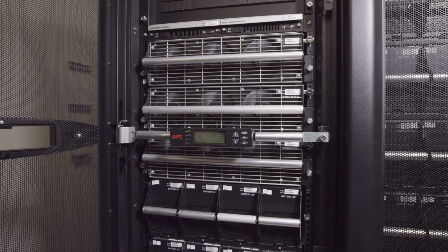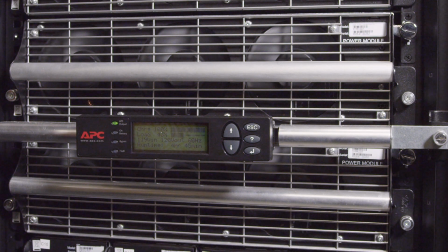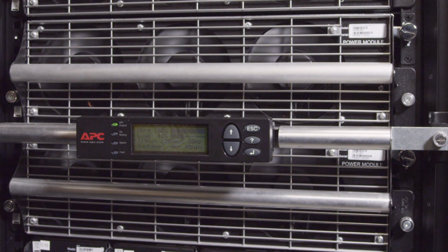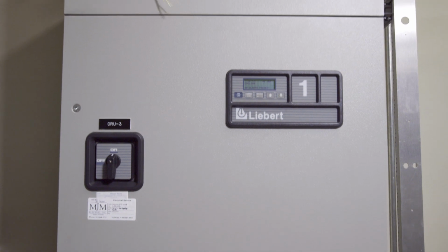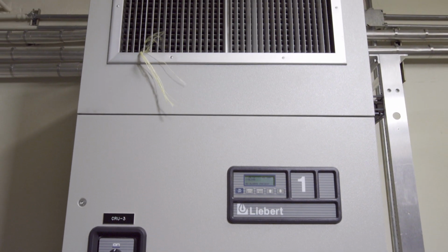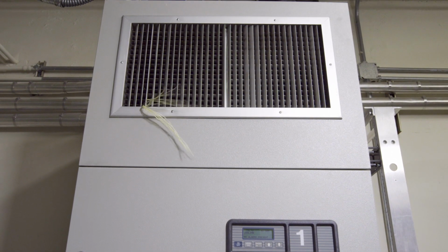The node itself has a dedicated generator, and a UPS capable of running the room for at least 4 hours in the event of a power failure, including if the generator doesn't start, and sufficient redundant cooling to keep the room at around 72 degrees even if all but one of the air conditioning units fail.